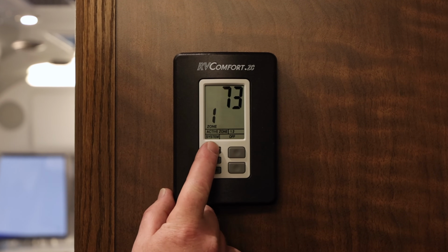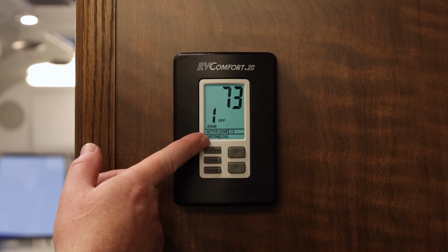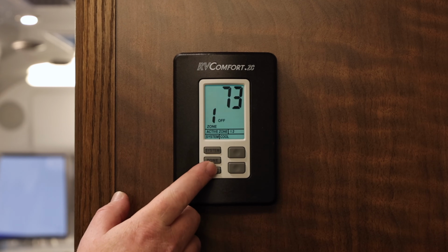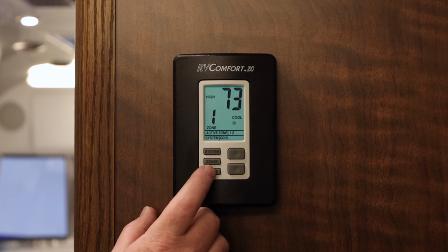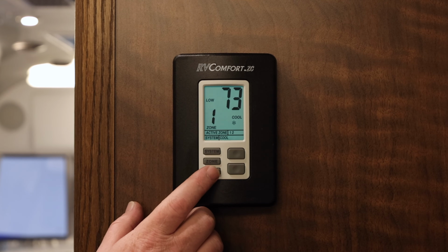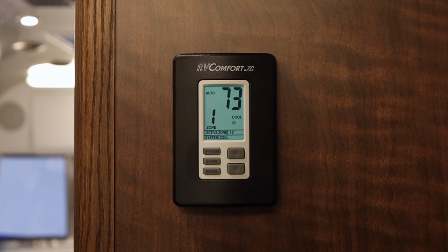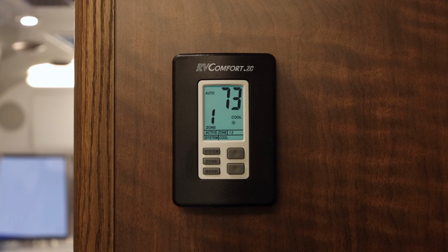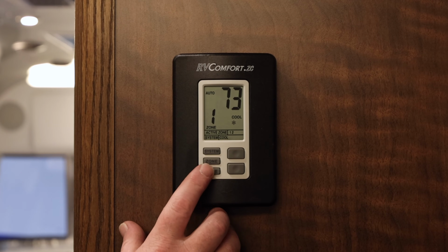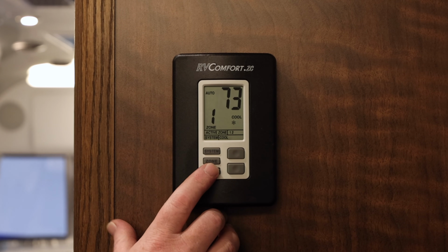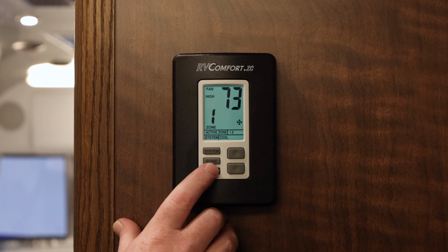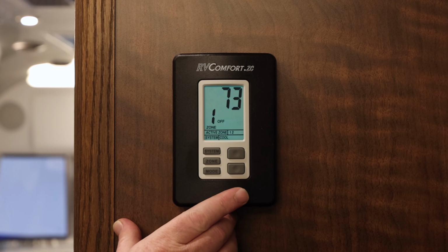So we'll hit the system button, and the first option we'll have is the air conditioner, and we'll use the mode to turn the high fan on, and then you want to go to low fan, and then after that, you'll settle on auto. Give it a moment to kick in, just like so. Now, after you've got the air conditioner kicking, if you want to turn the compressor off, you can run the fan just by itself. You've got a high and a low option, and then you're going to turn it off.